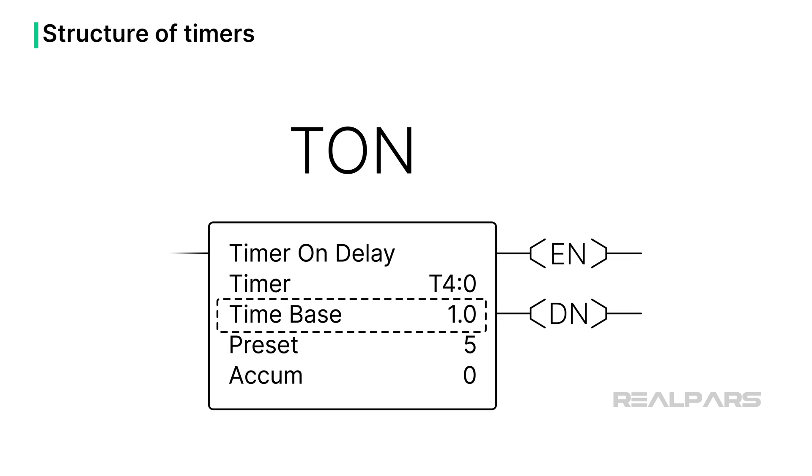The time base is the smallest unit of time tracked by the timer, such as 1.0 seconds, 0.1 seconds, or 0.01 seconds. The preset is the timer setpoint. The accumulated value is the elapsed time. All of these parameters are built into the timer function.